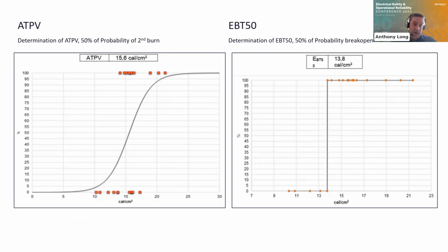Okay, so in that garment alone, the fabric weight was the same on initial receival. When it was washed, it was still the same weight as the previous test. The test was conducted exactly the same, but we've got a 2 cal, 3 cal jump in protection level of the polo shirt. Okay. So the ELIM is the ELIM on the day that fabric was tested. If you tested that fabric twice on the same day, you would get a different ELIM rating every single time. So every single time we test a fabric, we get a different arc rating virtually every single time.